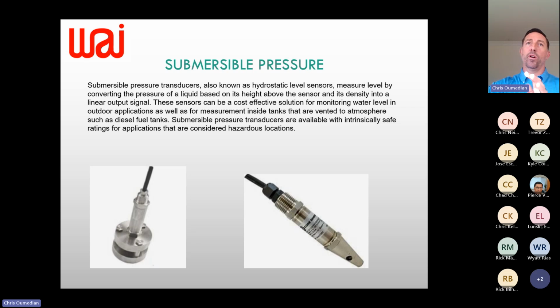These can also be ported in a standard pressure transducer at the bottom of the tank. Now, the premise is a pressure transducer gives you an amount of pressure, right? So if you're measuring air or liquid or whatever in a pipe, you're going to get a pressure output. With a tank, you put it at the bottom of that tank, either through the side or drop it in with that bullet, and you're going to get a pressure with gravity as that tank level goes up and down. That pressure is going to go up and down.